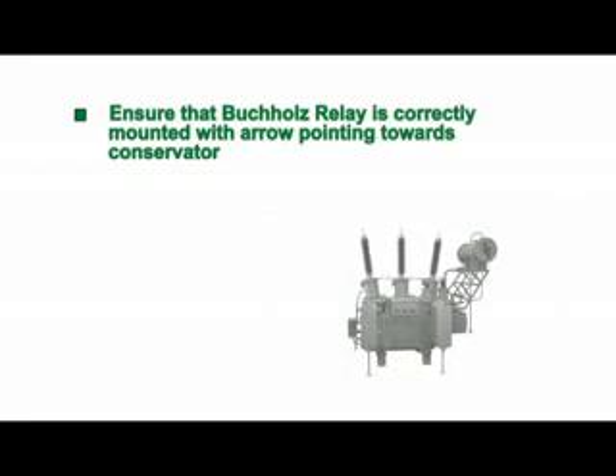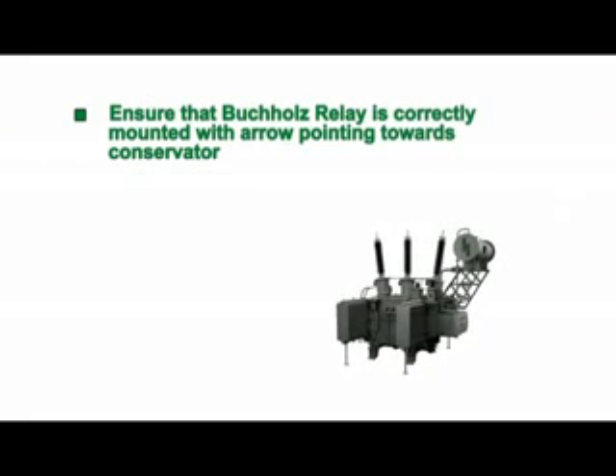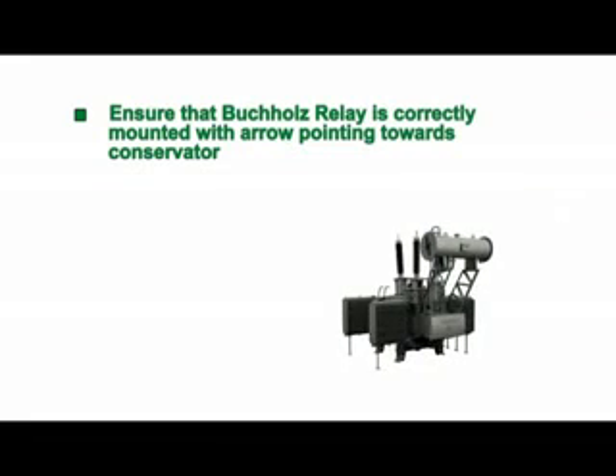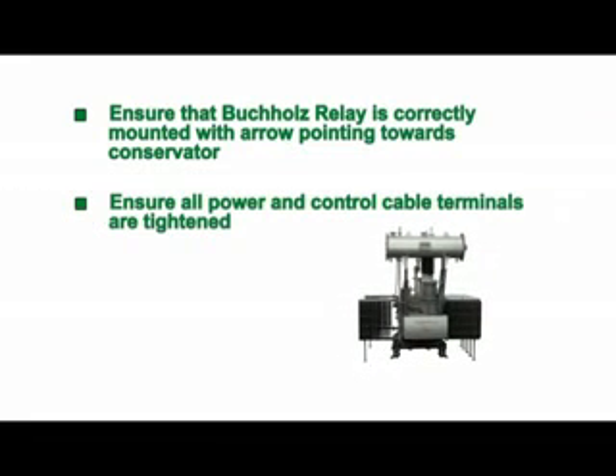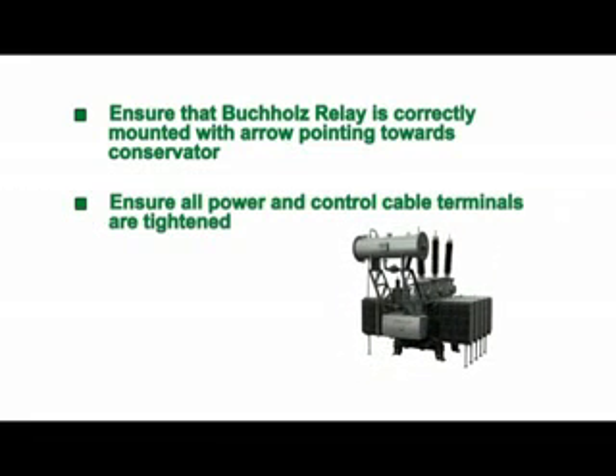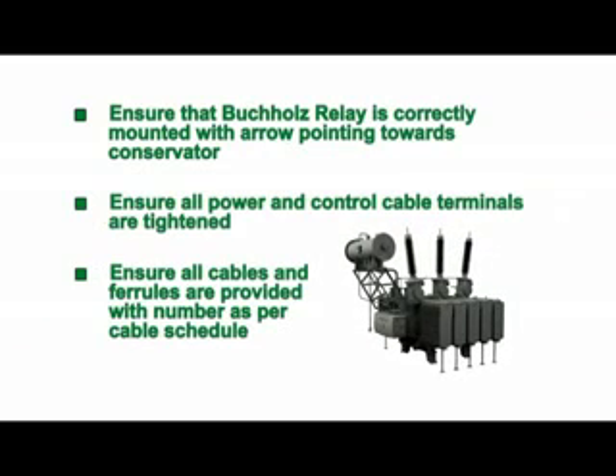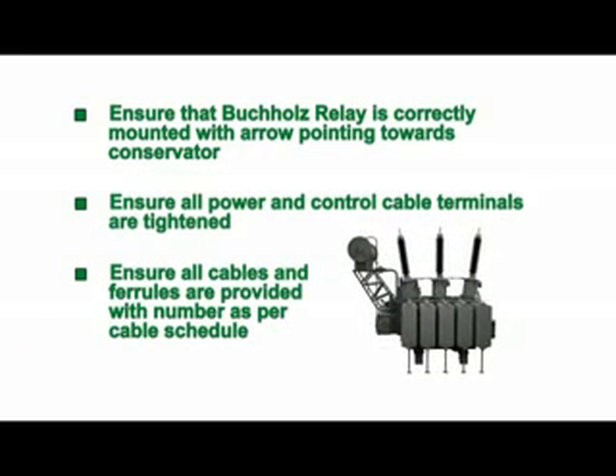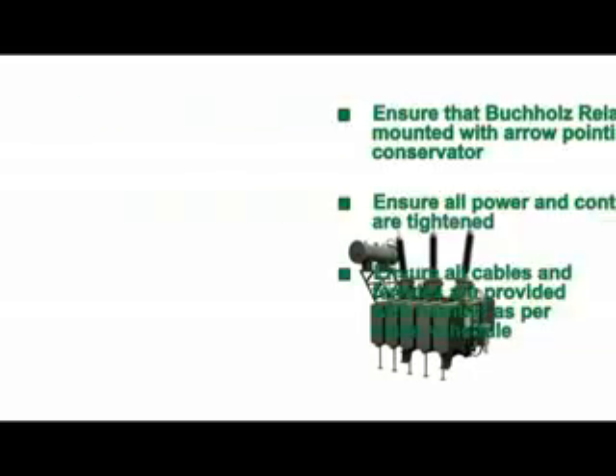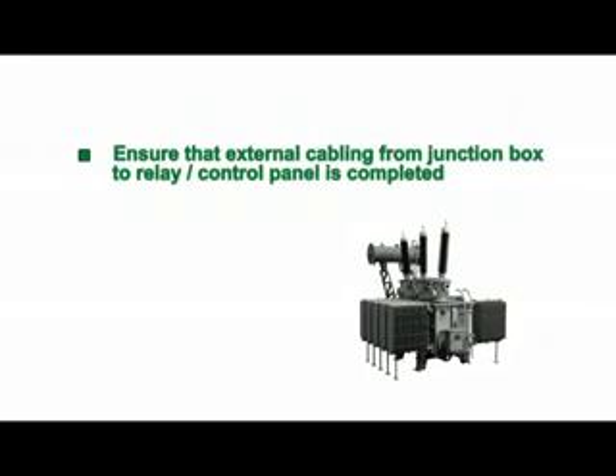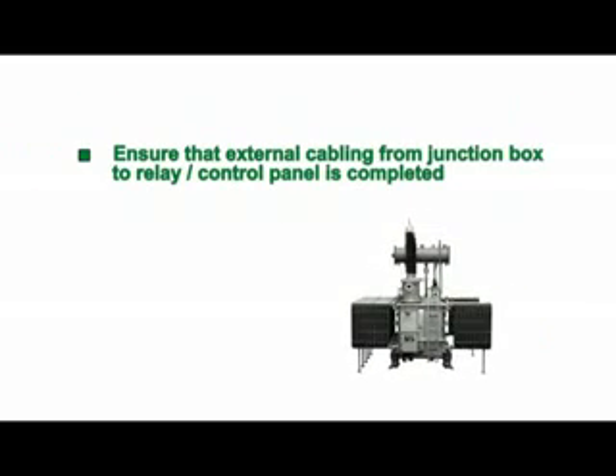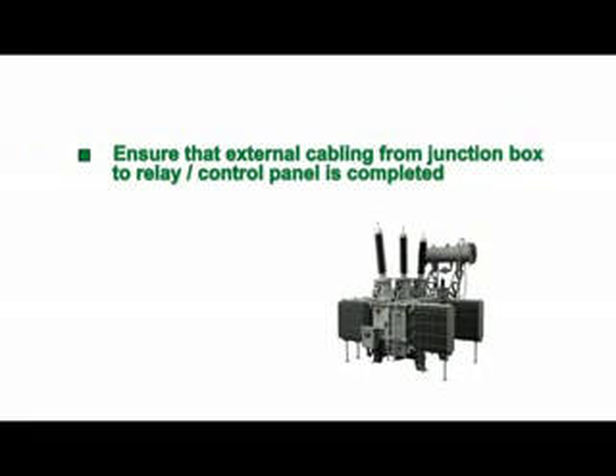Ensure that the Buchholz relay is correctly mounted with the arrow pointing towards the conservator. Ensure all power and control cable terminals are tightened. Ensure all cables and ferrules are provided with numbers as per the cable schedule. Ensure that external cabling from the junction box to the relay control panel is completed.